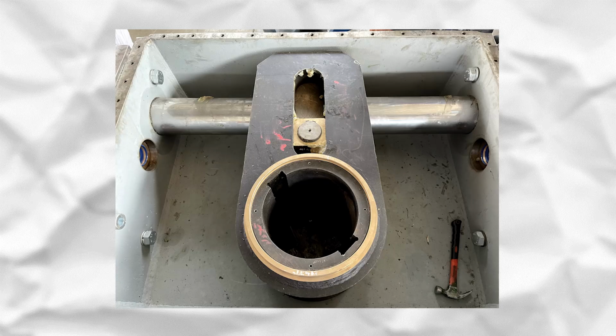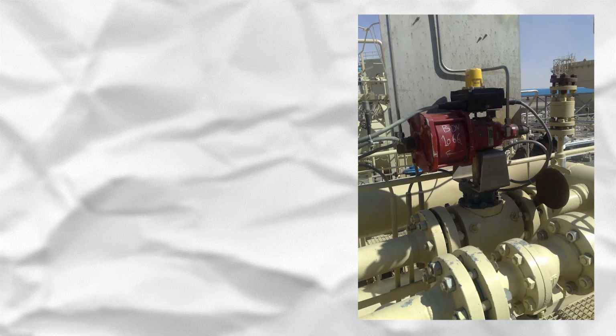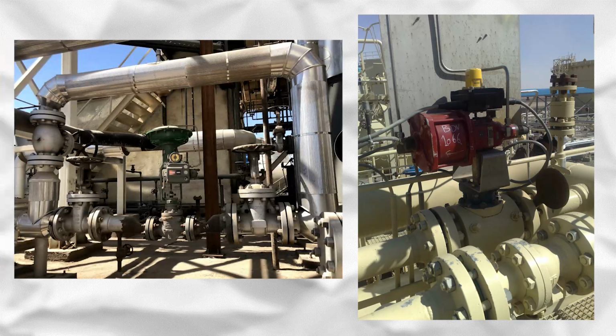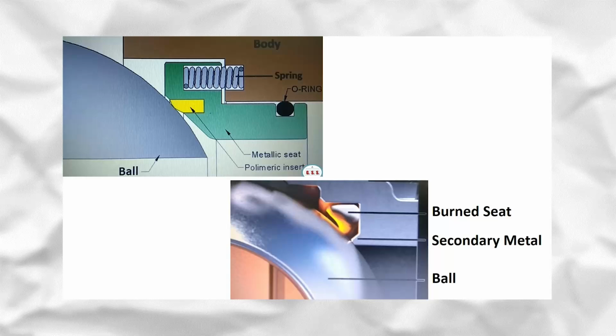to transform the axial movement to the rotary action. Generally speaking, the leakage class for the on and off valve must be selected from higher classes, 5 or 6. On and off valve size is equal to pipe size. It is different from the control valve size, which is always smaller than pipe size. In special applications where explosive fluid is passing through the pipe, the on and off valve must be designed fire-safe. In this regard, the seats are designed in a way that can provide the highest rate of isolation in spite of burning the soft seat. I've just said soft seat.